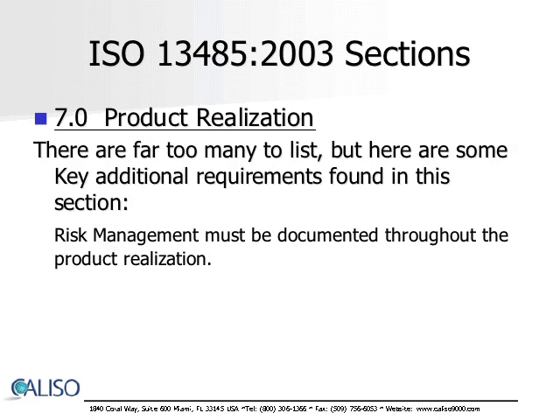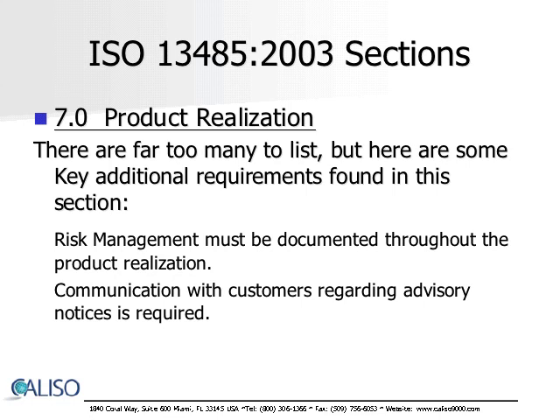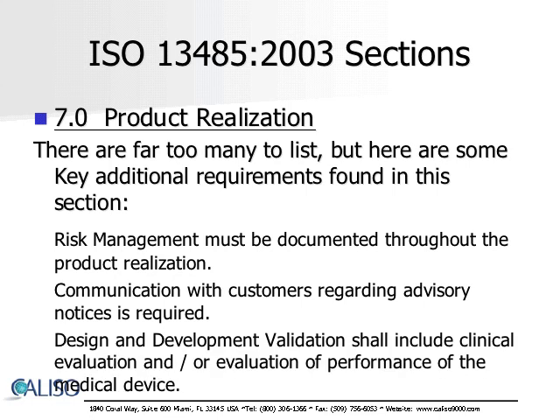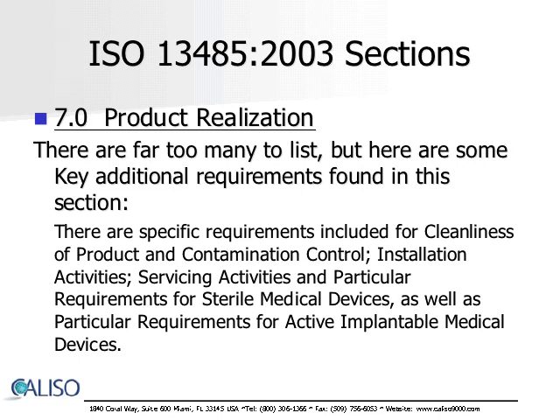There are far too many additional requirements to list, but here are a few found in this section. Risk management must be documented throughout product realization — please reference ISO 14971 for details. Communication with customers regarding advisory notices is required. Design and development validation shall include clinical evaluation and/or evaluation of performance of the medical device. There are specific requirements for cleanliness of product and contamination control, installation and servicing activities as applicable, and particular requirements for sterile medical devices as well as active implantable medical devices.